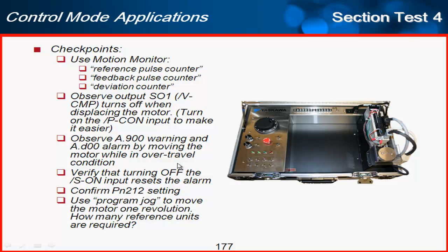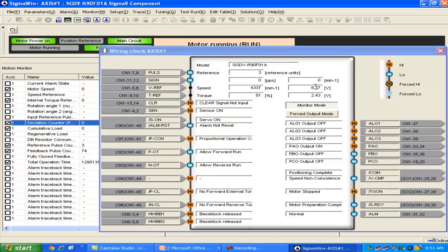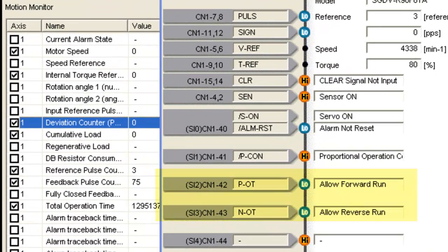The other feature that had to do with position error was to get a warning or an alarm by moving the motor in over travel. This could happen during motion, but to test it out, it's really hard to overpower the motor by 45 or 90 degrees unless you put the demo into over travel condition. So let's keep an eye now on the deviation counter and I'll hit the over travel inputs. You can see I've done that. Now I'll start to turn the motor. You can see the deviation counter now is going way up. That's the position error, going way up. So 4278 means 42.78.